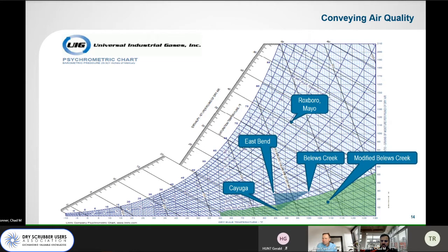We were able to modify the settings on the dryer for Belews Creek and brought that down to within the safe green zone, below 8% relative humidity, and moisture, scaling and pluggage issues haven't been an issue there. East Bend, which is a new system that we currently started up, was also modified to be within the 8% relative humidity, and it's been running since February with no pluggage or scaling to date.